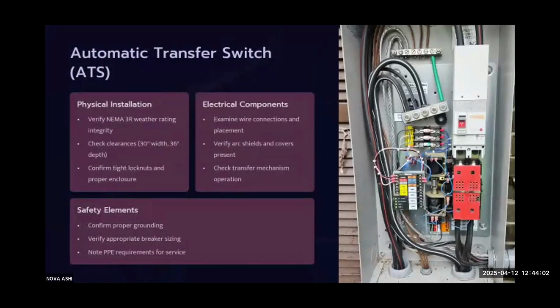Yes, sir. It is a transfer switch. So it says, of course, at the top, automatic transfer switch. So this is an ATS, of course, is short for that. As an inspector, when you're looking at a transfer switch outside, you want to make sure that it is maintaining its NEMA 3R rating. And that means no one has penetrated the top. You don't have water infiltration coming inside of the unit. And if you look inside this unit, you don't see any rust or anything of that nature. So water has not infiltrated this unit here.